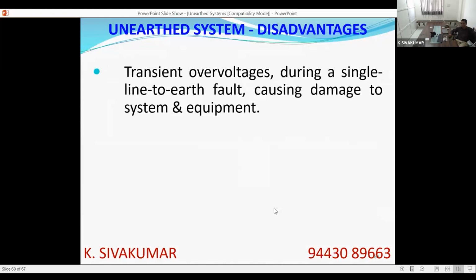So, summing up the disadvantages of the unearthed network, as we have seen in the previous slides, there will be huge transient overvoltages during a single line to ground fault, causing damage to system and equipment, because we cannot design our system to tolerate this high voltage, as it will make our system and equipment costly. So we generally economize in our design. So when we design our system for tolerating nominal overvoltages, and in an unearthed system this happens, system and equipment get damaged.